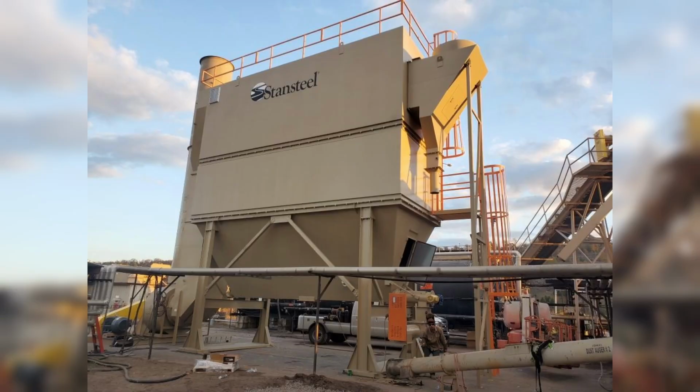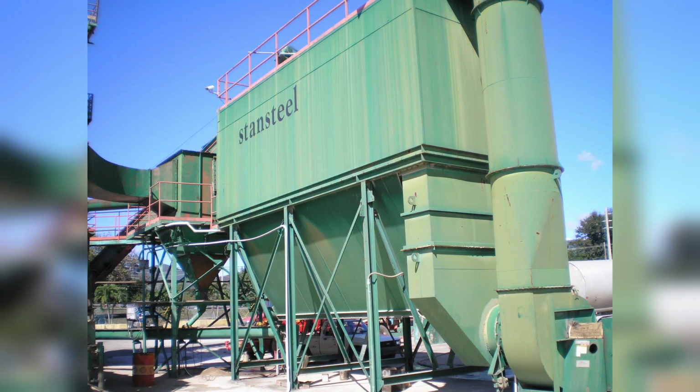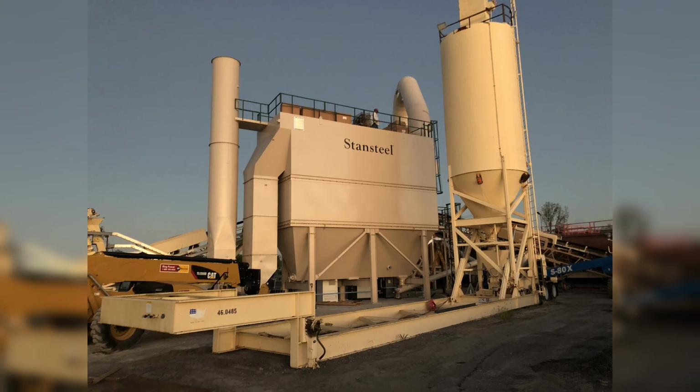Yeah. If we're sizing new equipment, how big should the baghouse be? It's a question I've been asked so many times, and my canned answer is typically, how big of a baghouse or how large of an air system do we need? My answer is bigger's better, until you get really financially stupid or we have to start insulating the baghouse because of dew point problems. Eventually you'll get there. If you get down to maybe a 2-to-1 or something, you get to be so massive you can't keep the thing hot. We'll talk about those.